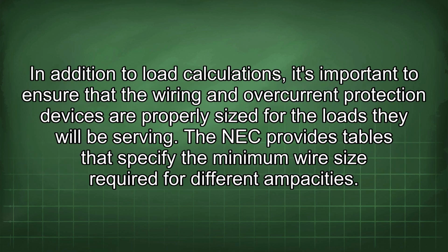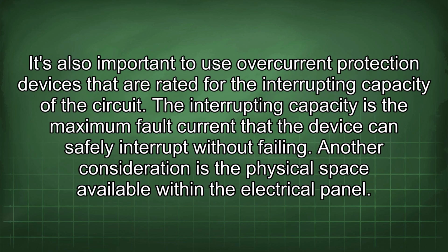In addition to load calculations, it's important to ensure that the wiring and overcurrent protection devices are properly sized for the loads they will be serving. The NEC provides tables that specify the minimum wire size required for different ampacities. It's also important to use overcurrent protection devices that are rated for the interrupting capacity of the circuit. The interrupting capacity is the maximum fault current that the device can safely interrupt without failing.